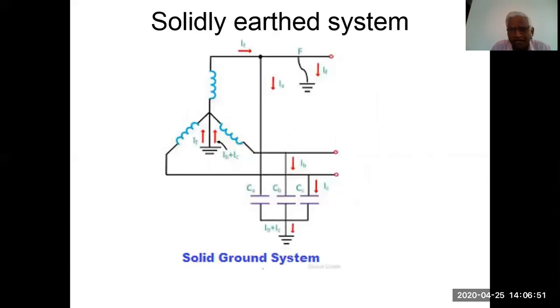Now you can see the solidly earthed system is a star connected transformer. The star point has been grounded. When there is a ground fault in one of the phases, the current goes through the earth and back. So this is almost like a short circuit, and there is a heavy current flowing, based on the impedance of the transformer. Transformer impedance is always written on the nameplate. For a distribution transformer, the impedance is around 5%. So there is a current flowing through this that will blow the fuse in the shortest possible time, and the system is disconnected from the transformer.